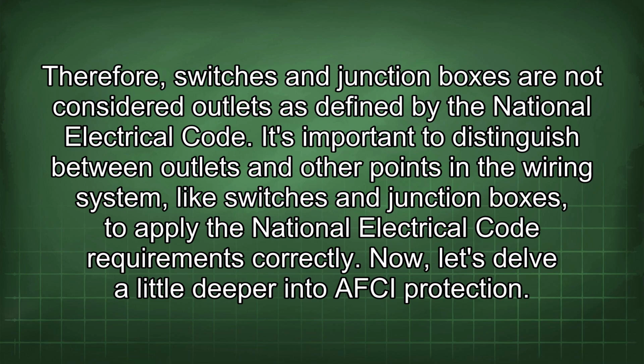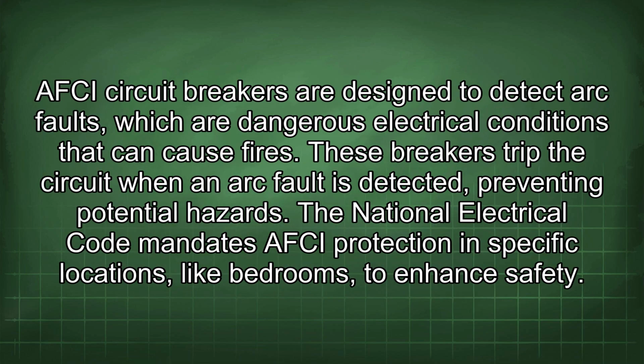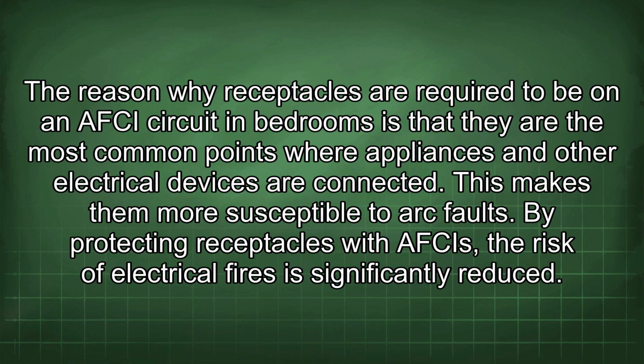Now let's delve a little deeper into AFCI protection. AFCI circuit breakers are designed to detect arc faults, which are dangerous electrical conditions that can cause fires. These breakers trip the circuit when an arc fault is detected, preventing potential hazards. The National Electrical Code mandates AFCI protection in specific locations, like bedrooms, to enhance safety. The reason why receptacles are required to be on an AFCI circuit in bedrooms is that they are the most common points where appliances and other electrical devices are connected. This makes them more susceptible to arc faults. By protecting receptacles with AFCIs, the risk of electrical fires is significantly reduced.